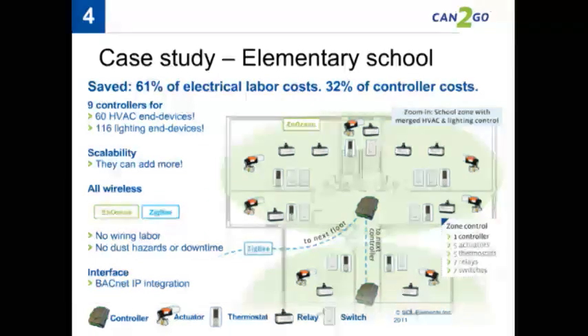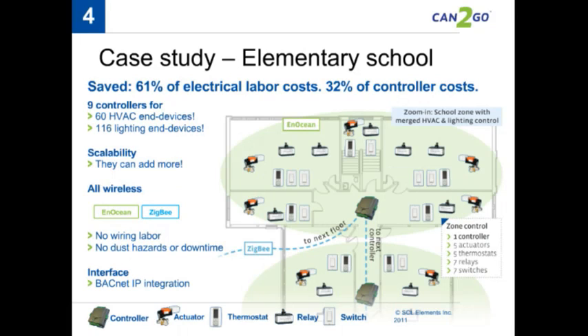And this is what they did: they deployed throughout the whole building only 9 controllers to handle both HVAC and lighting. The controllers were handling 60 HVAC end devices — actuators and thermostats — and 116 lighting end devices, meaning lighting relays or lighting switches. So as you can see, this was a fairly standard building automation solution.